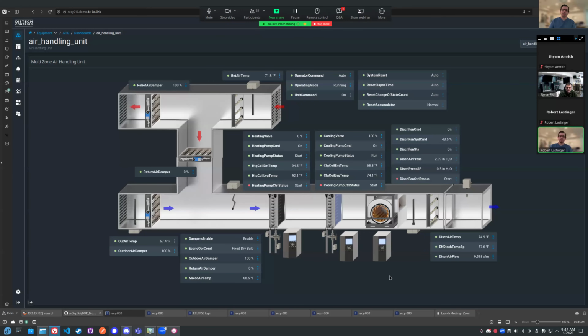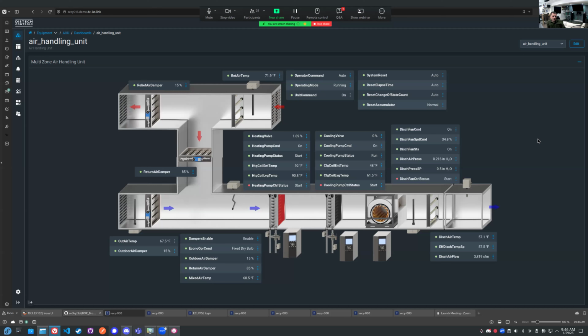If you didn't run one of those virtual VAVs, or didn't run that mechanical piece of equipment, how does this interact? In this setup, we have all the equipment, the air handler and the VAVs. If I just wanted to focus on the air handler and didn't care about the VAVs, I could run it in a way that only interacts with the air handler. Since you already built control algorithms in the model, the VAVs will just be controlled by the model and do their thing. I don't have to touch them. So I can take pieces of the model and interact with it, leaving the rest alone if I want. It's flexible in that way.